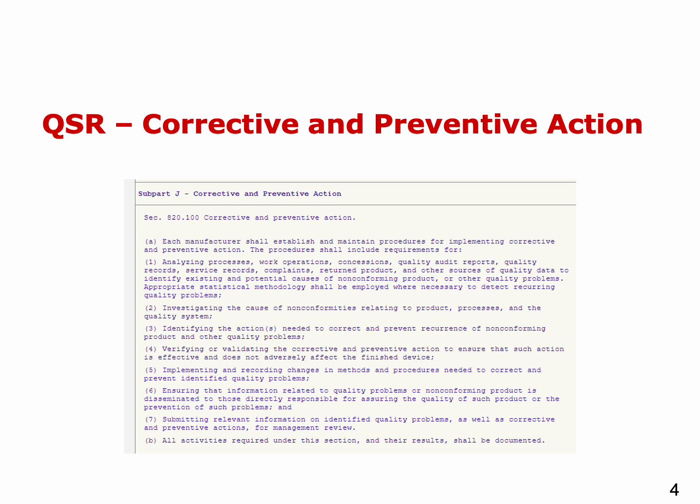Now let's look into FDA regulations. Here we are looking into 21 CFR, section 820.100, subpart J, related to corrective and preventive actions, similar to ISO 9001, clauses 8.5.1, 2, and 3. Now here I'm going to read what is required by the FDA, by USA government. Each manufacturer shall establish and maintain procedures for implementing corrective and preventive actions.